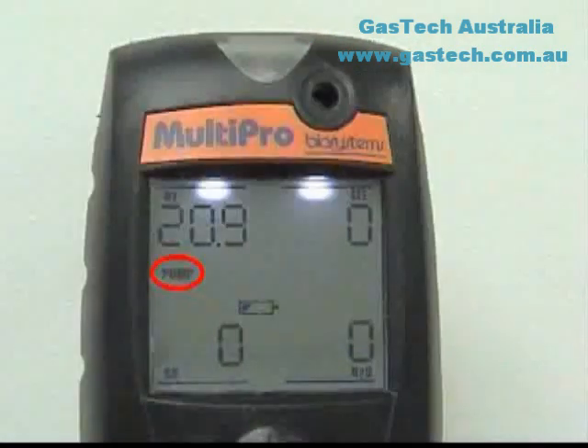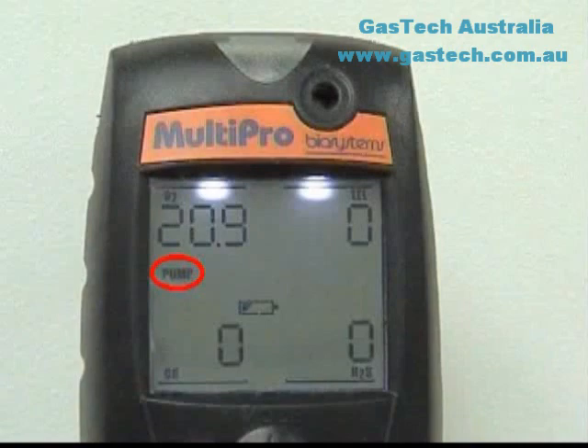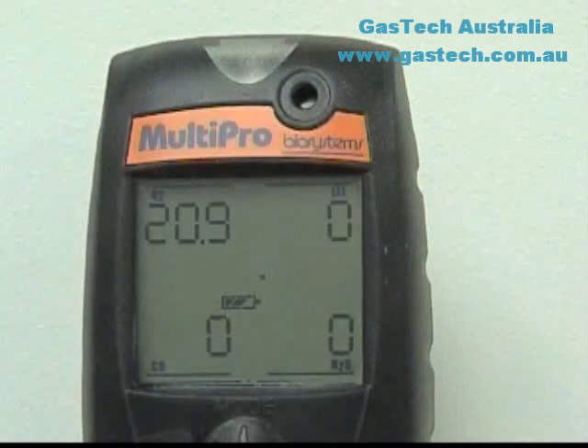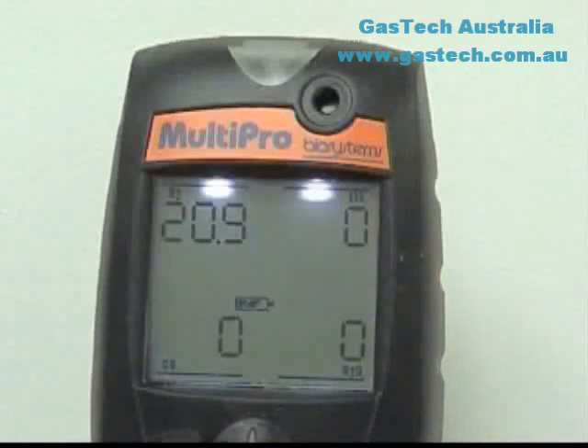The word pump will be shown at the left center edge of the display if the instrument detects a pump is attached. The battery icon at the lower center of the display gives an indication of the remaining battery strength. When the battery icon is empty, it is time to either change or recharge the batteries. To turn on the backlight, just press the mode button once. To view the max readings screen, press the mode button once to turn on the backlight, and then once more.